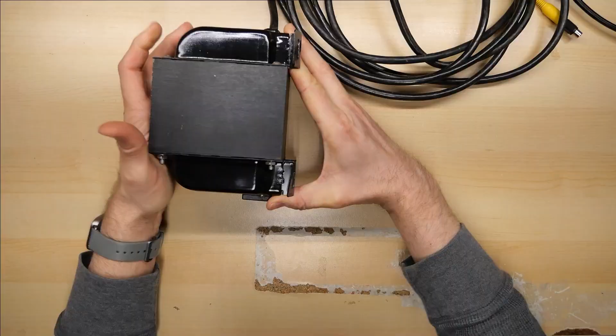An isolation transformer is a transformer like any other, with a primary side and a secondary side. The primary connects to the mains, and the secondary connects to your load. Most transformers, like a 9-volt AC transformer in a Commodore 64 power supply, take 120 or 220 volts in and output roughly 9 volts AC. It's all about the difference in the number of turns around the core from one side to the other. What's cool about transformers, even the 9-volt AC type, is that the high side and the low side are separated.